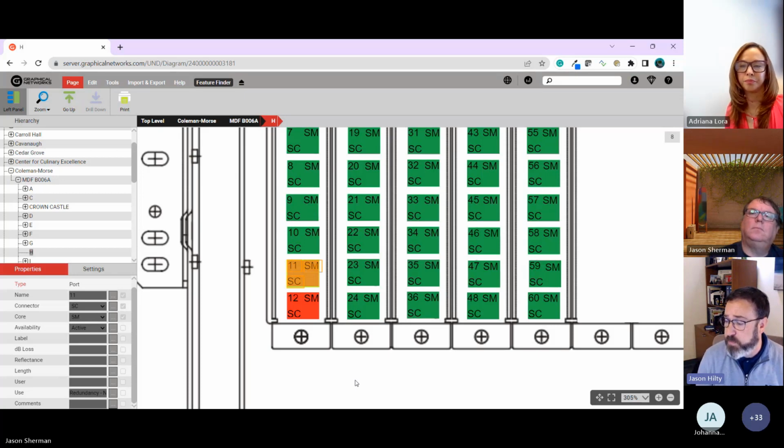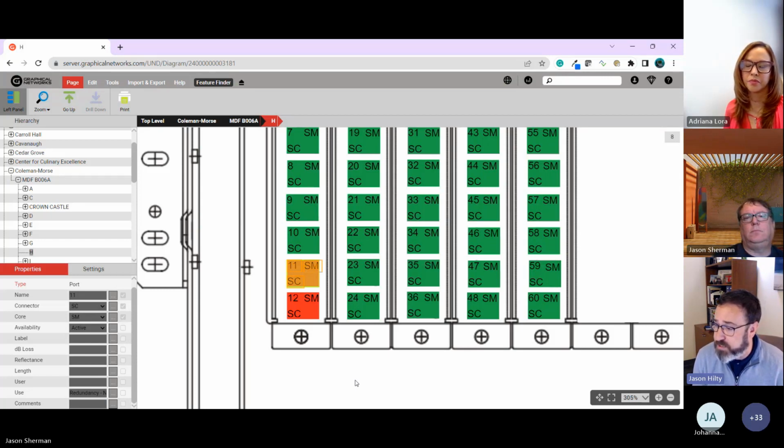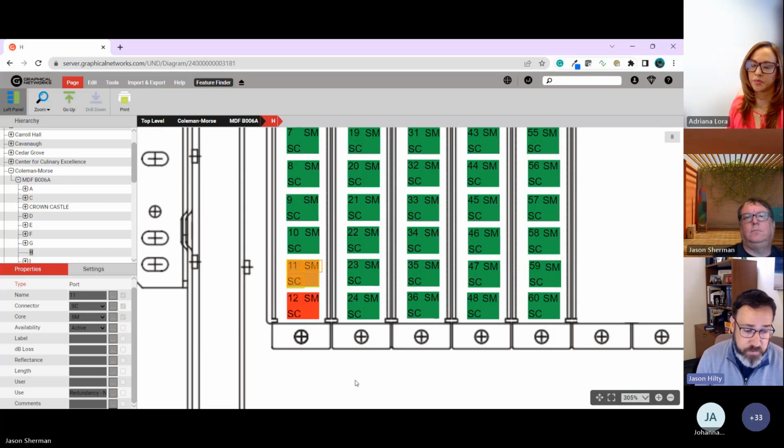You can use it, for example, if it was tested last year and you saw negative 1.5, but now you've got a failure. Well, obviously something's changed. What's changed since then? Did someone damage something? So there's a lot of good information there to reference.